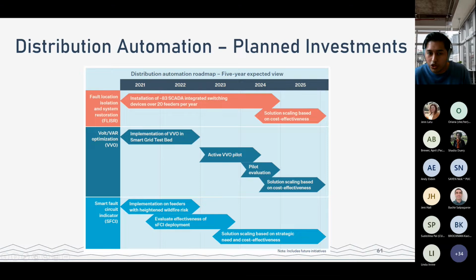We talk about distribution automation, which is actually a set of three different initiatives. We have fault location, isolation, and system restoration, or FLISR, which tries to isolate a fault within a section of a feeder, preventing everyone downstream from having an outage, restricting the number of people impacted by an outage, say from a tree falling. It also provides automatic system restoration for smaller things, such as a small branch falling on the wires and causing a trip.